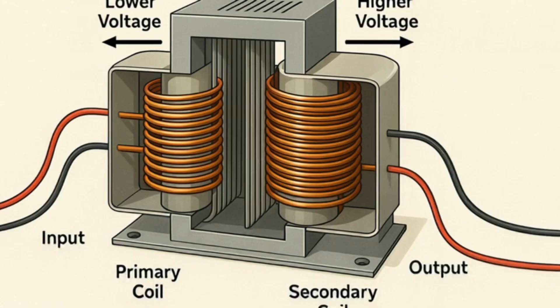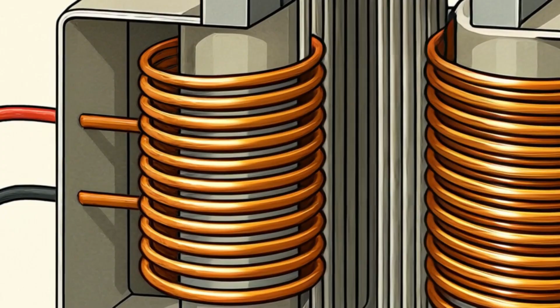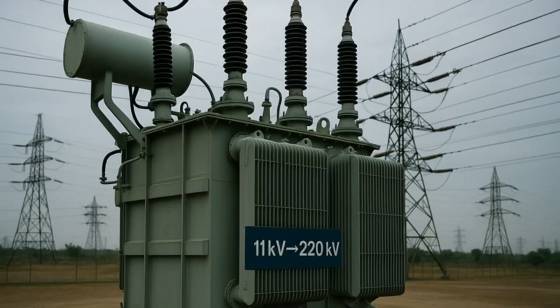But 11 kV can't go far. It fades, it gets lost as heat. So comes the next hero, the step-up transformer. Massive coils, soaked in insulating oil, boost the voltage to 220,000, 400,000, even 765,000 volts. Why? Because higher voltage equals lower loss.